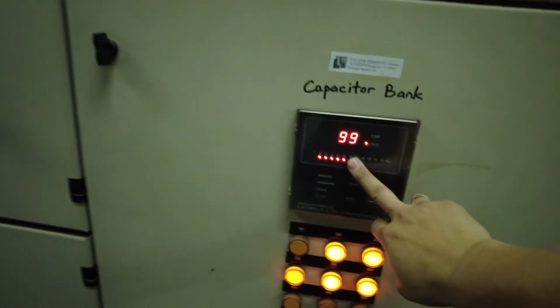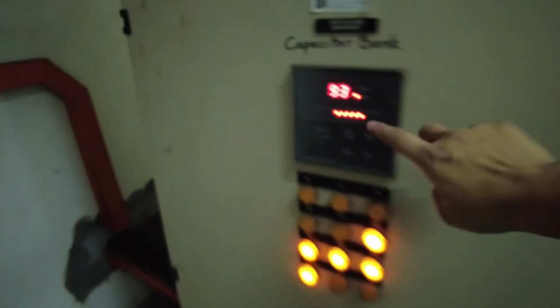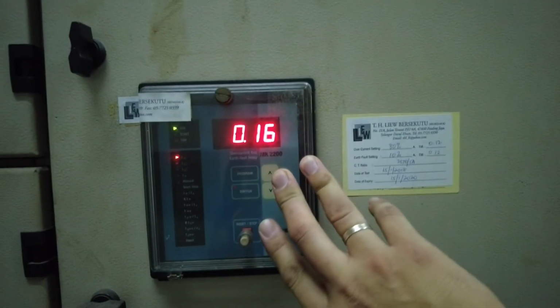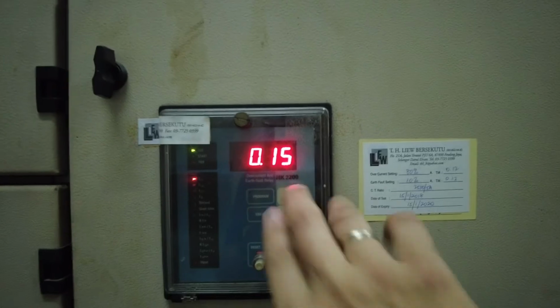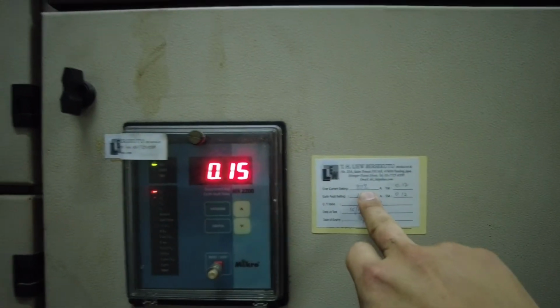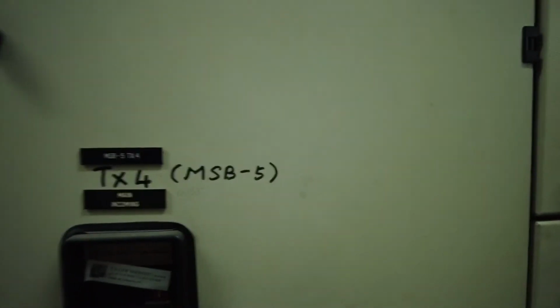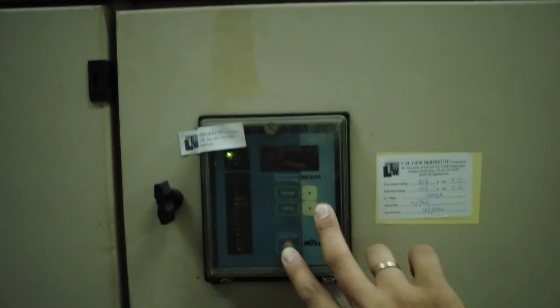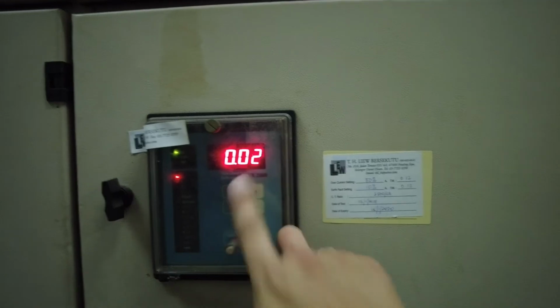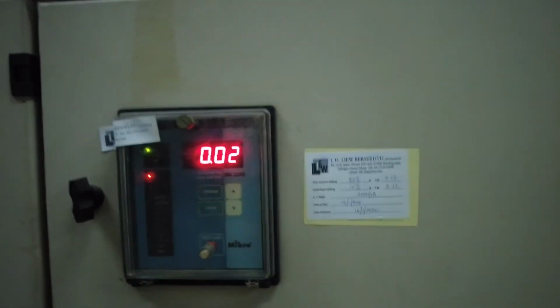In the meantime, check the power factor. Make sure no undercompensation. Check the main incomer ACB protection relay. Check the load, 15%, overcurrent 80%, so no overloading. This is another MSB. 2% load only. Overcurrent setting 80%.